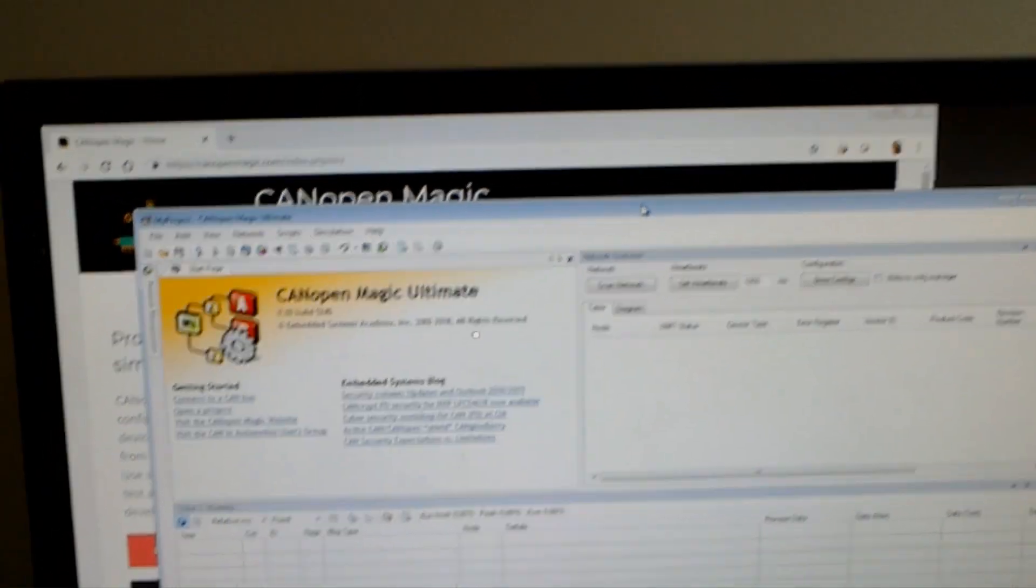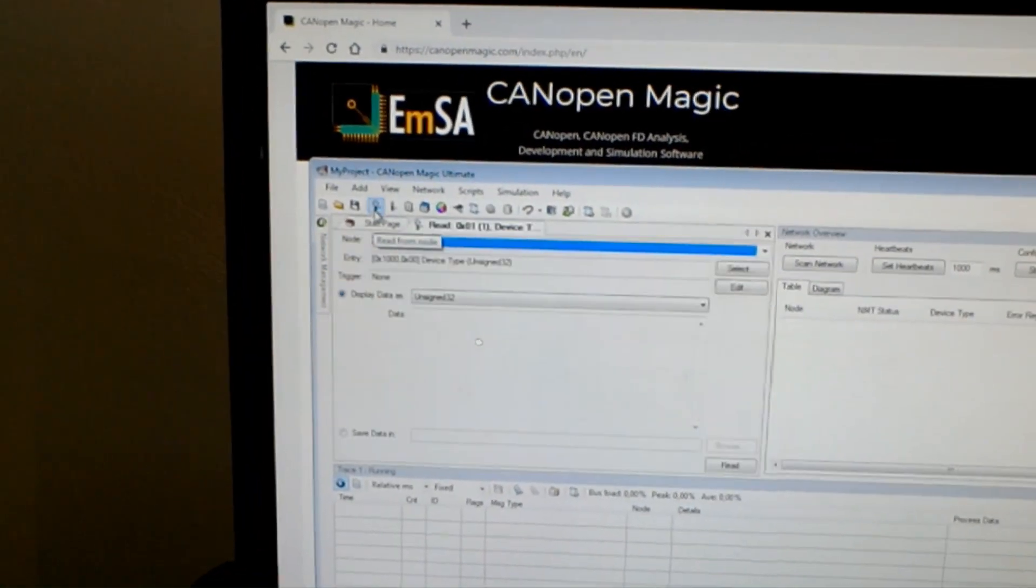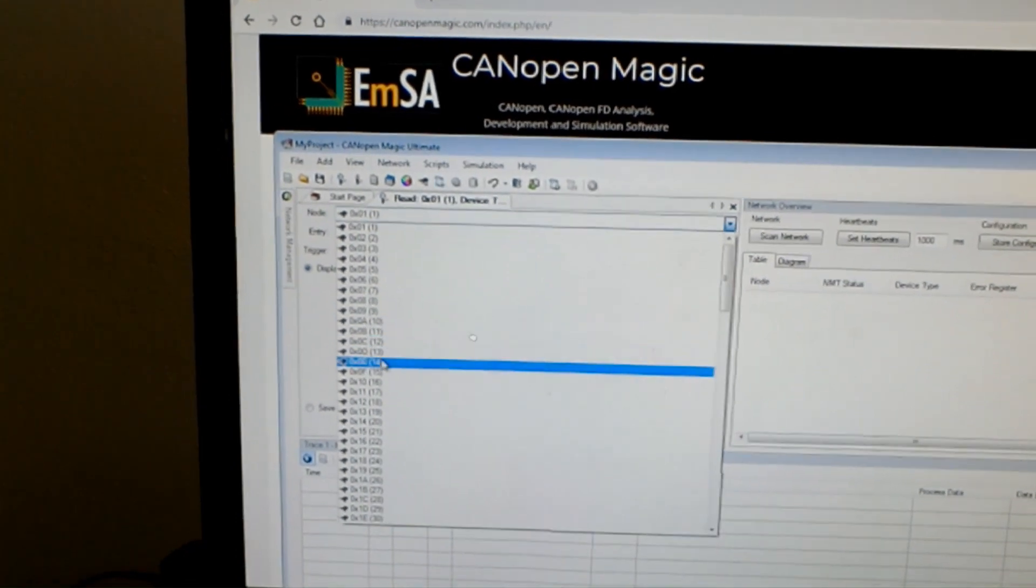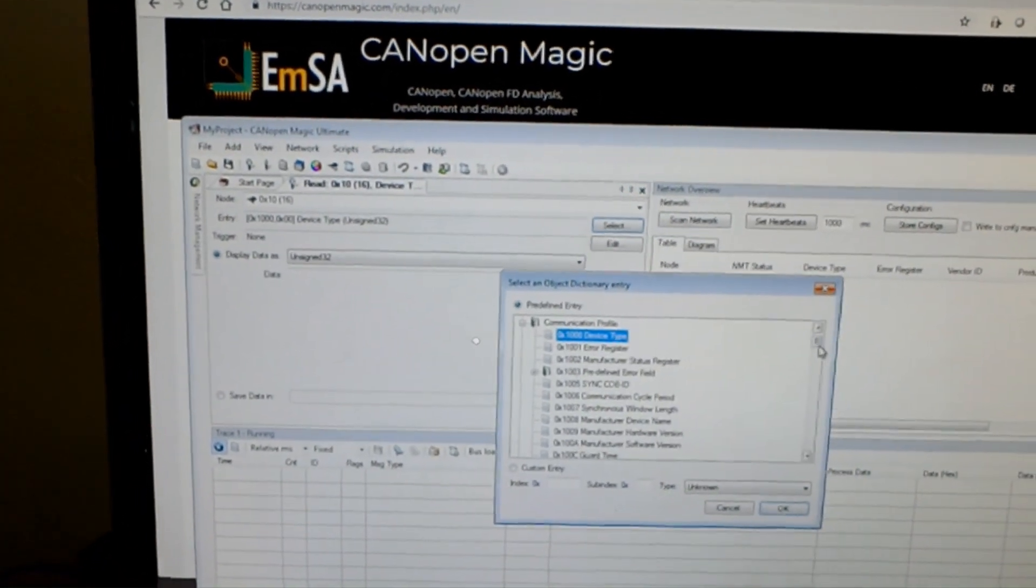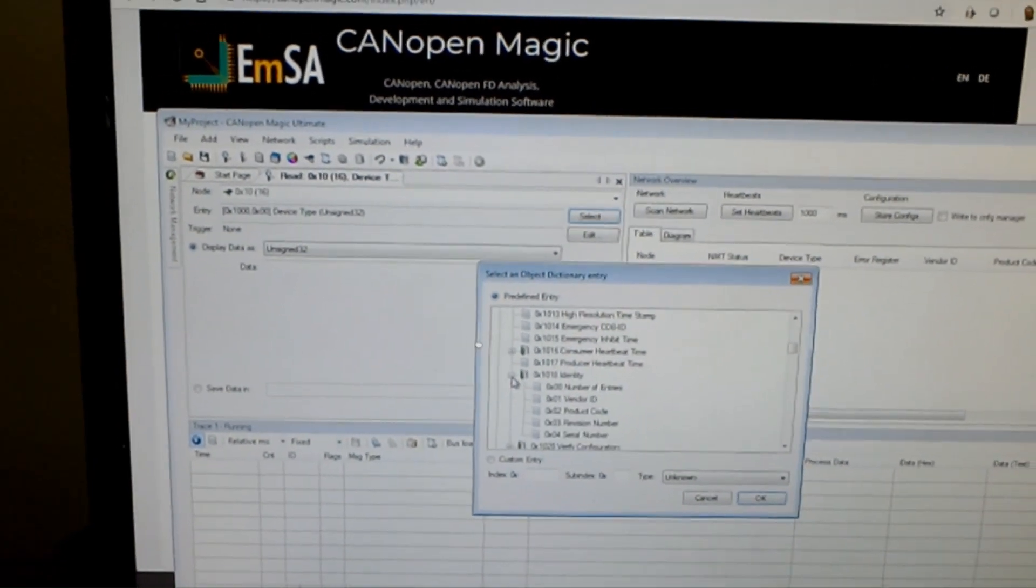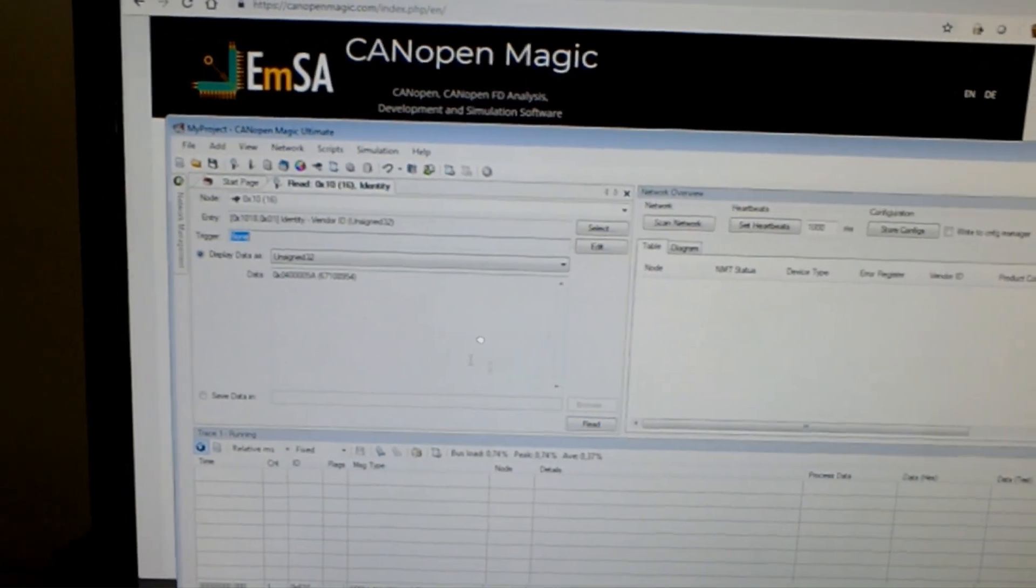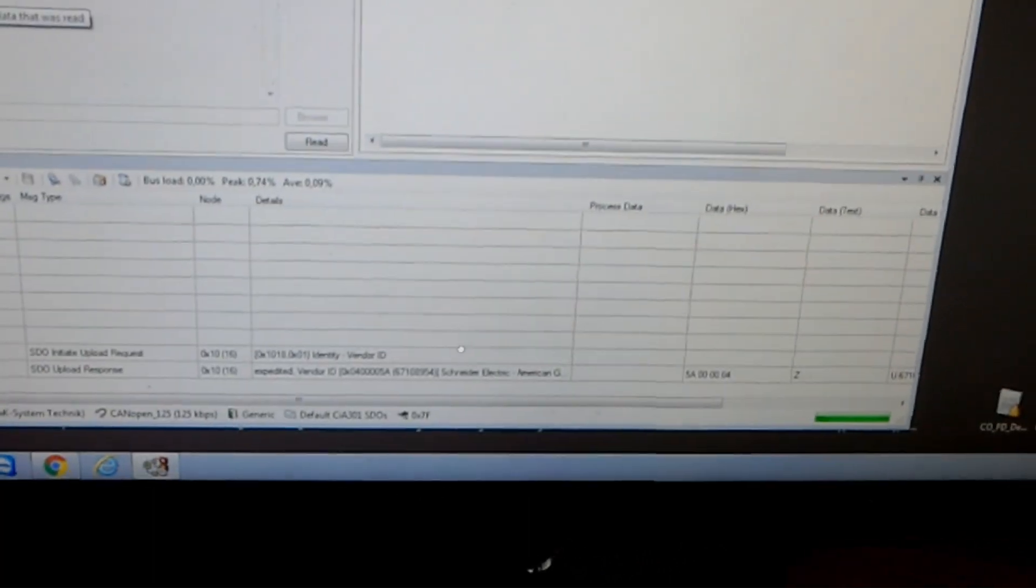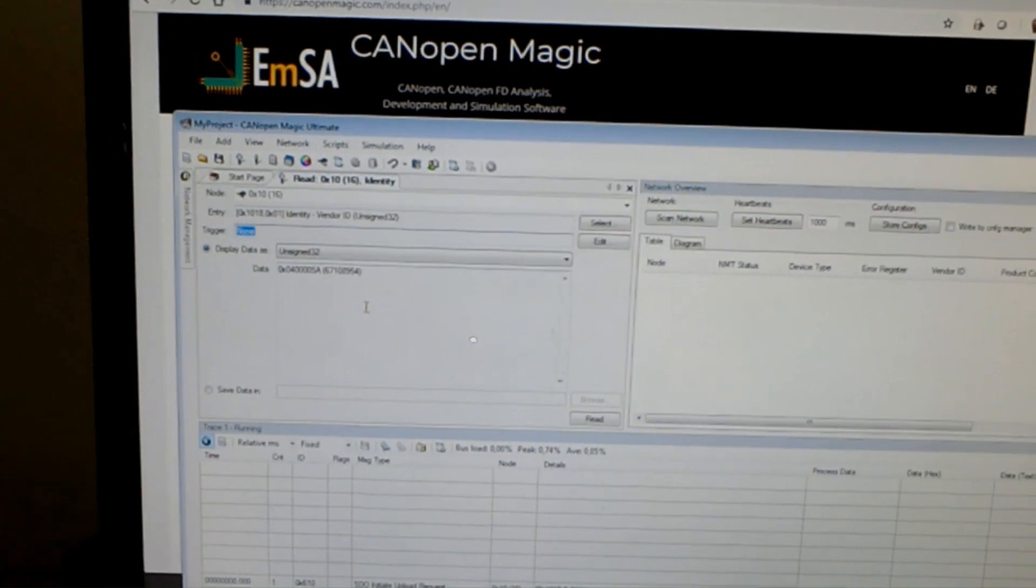Let's open up CANOpenMagic and first let's do a read. I select the read tab, select node ID 0x10 and select the entry we want to read. For example, let's say 1018, the vendor ID. If we hit read, here is the number and if we look down here in the trace, it belongs to Schneider Electric, so we have a Schneider Electric device here.